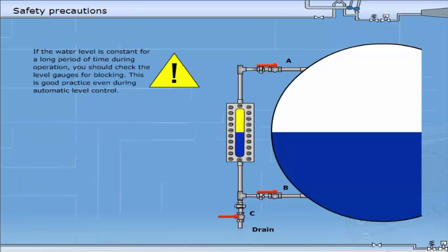If the water level is constant for a long period of time during operation, you should check the level gauges for blocking.